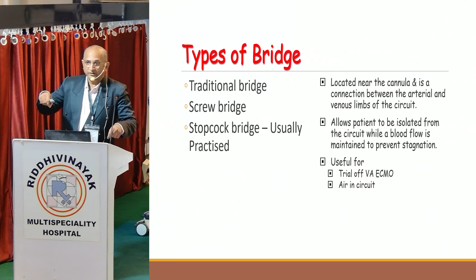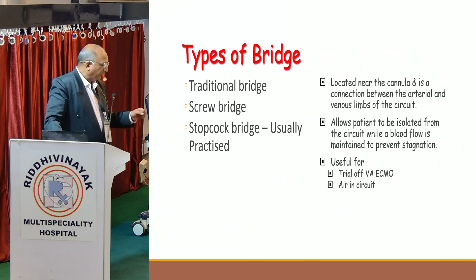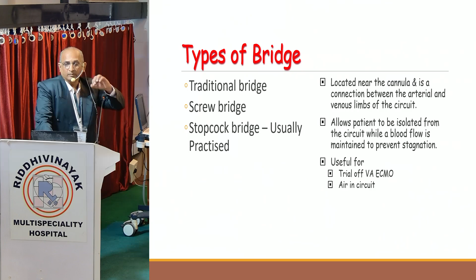So you can stop the bridge and you can take the air in the bridge. And the third advantage of this bridge is, suppose suddenly your circuit stops and you don't know where the clot is, whether it's in the cannula or in the oxygenator or something, you can separate the patient and open the bridge. If the circuit is moving well, it means something is wrong with the cannula. If the circuit is not moving, it means something is wrong with the pump or oxygenator. So that is where it helps.